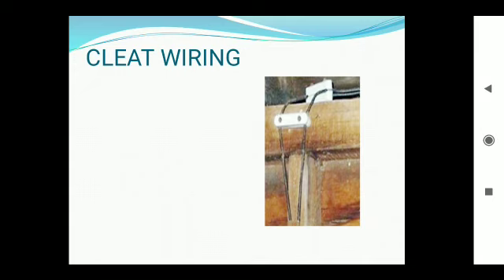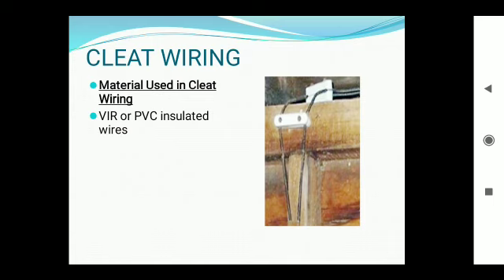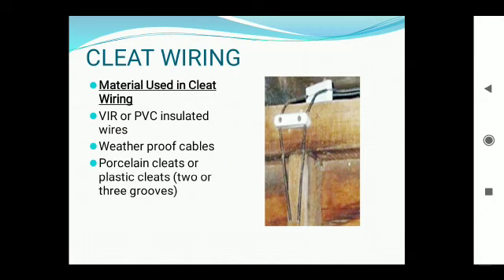So number 1, the cleat wiring. This is the simplest and cheapest wiring system, and it is a temporary wiring. The materials used in cleat wiring are VIR or PVC insulated wires, that means polyvinyl chloride insulated wires, weatherproof cables, porcelain cleats or plastic cleats, and screws.